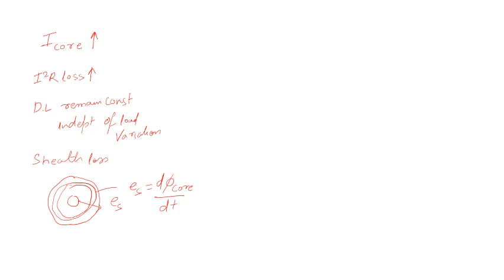So if your core current changes, the flux will change. If it increases, the EMF induced will also increase, and if the EMF increases, sheath loss will also increase.